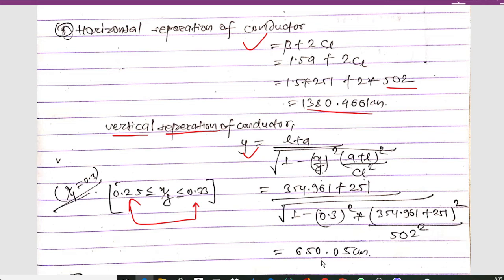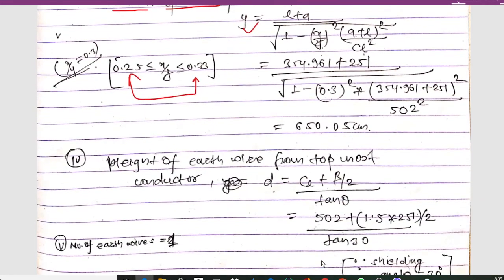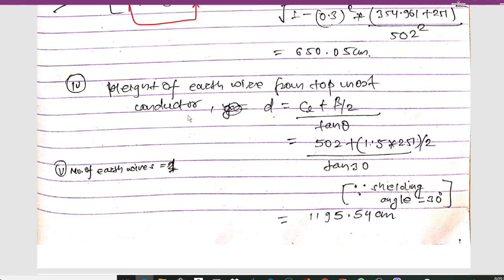To calculate the height of the earth wire from the topmost conductor, the formula is: d = (CL + β/2) / tan θ, where θ is the shielding angle. We assume a shielding angle of 30 degrees. Substituting all values, we get d = 1195.54 centimeters. The number of earth wires in this case will be one.